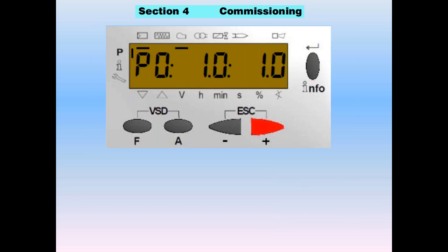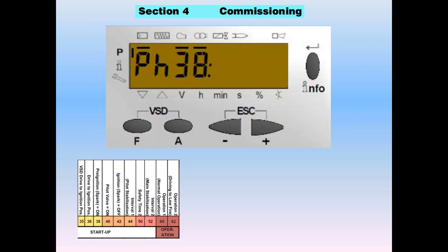Sequence through purge and hold at P0. If you press plus from here, it starts to go into phase 38 and turns on the ignition. At the top of the display, a bar indicates the call for heat — the envelope. The blower symbol has a bar below it showing the blower is running. In phase 38, the ignition symbol has a bar below it saying ignition is energized. These status bars give you direct feedback from the LMV chassis about exactly what it's doing.